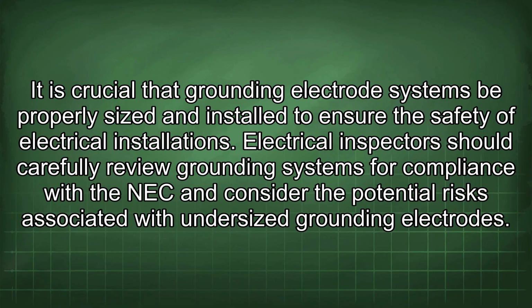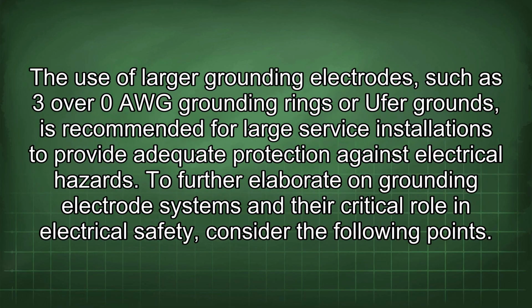Electrical inspectors should carefully review grounding systems for compliance with the NEC and consider the potential risks associated with undersized grounding electrodes. The use of larger grounding electrodes, such as 3/0 AWG grounding rings or UFER grounds, is recommended for large service installations to provide adequate protection against electrical hazards.